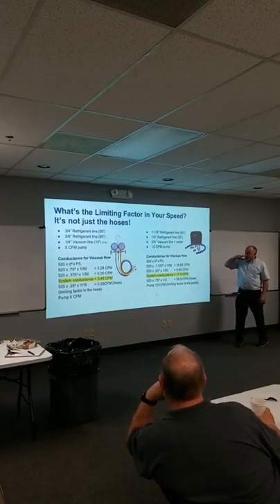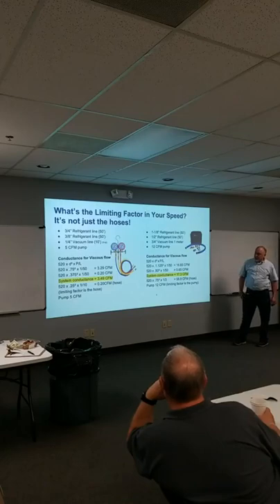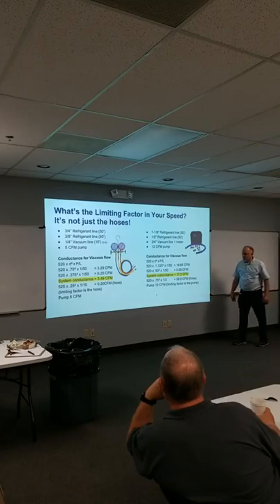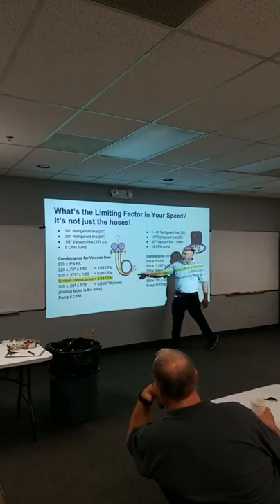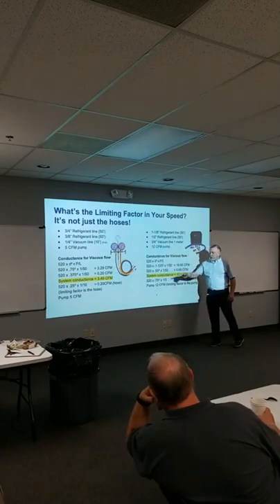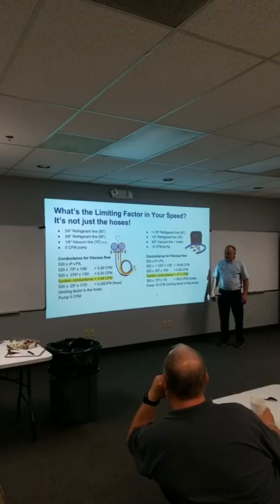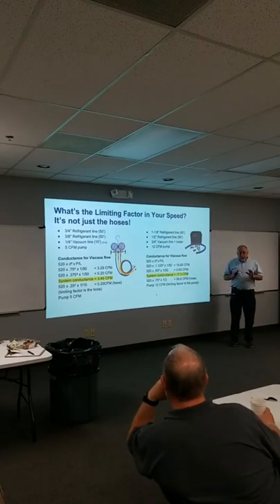It's not just your speed, you gotta also include your refrigerant line. So then I redid the math here and said, okay, well, 3/4 refrigerant line by 3/8, 50 foot of each, 1/4-inch vacuum line, 5 CFM pump. Do the math here and you say, well, I got a conductance speed of 3.29 CFM on the 3/4 tubing and 0.2 CFM on the 3/8. So you add those together, that's your system conductance of 3.49 CFM. So think about that for just a minute.